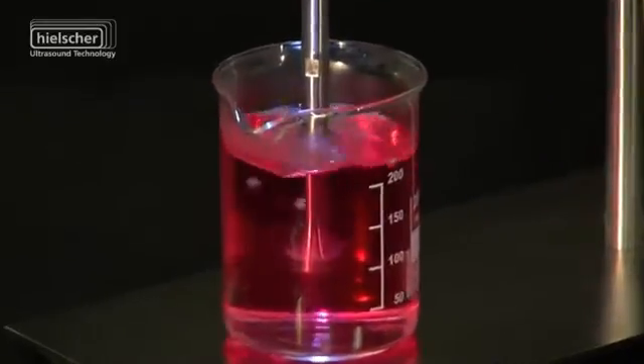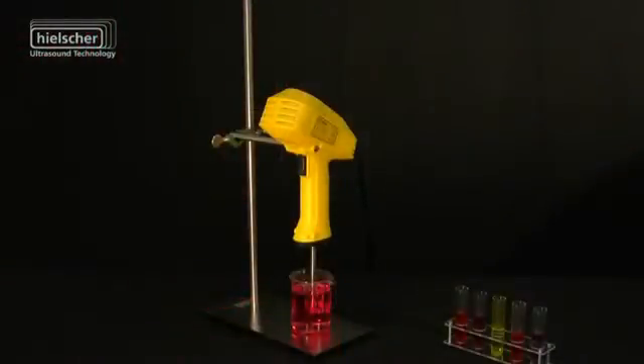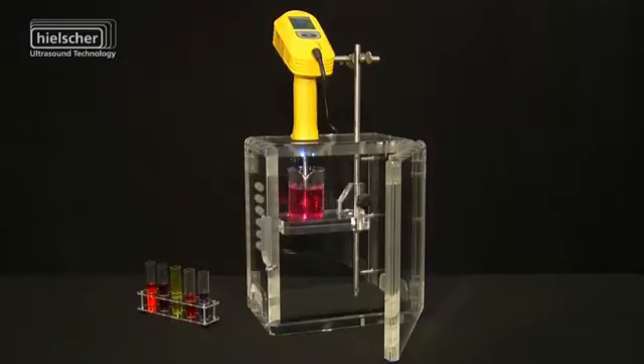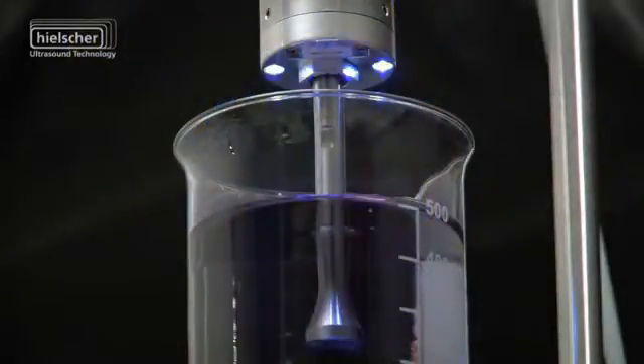Both models of the 200W ultrasonic devices can sonicate volumes from 0.1mL to 2000mL reliably. The new ergonomic and lightweight design means it can be used as a convenient hand-held device as well as classic laboratory support equipment.